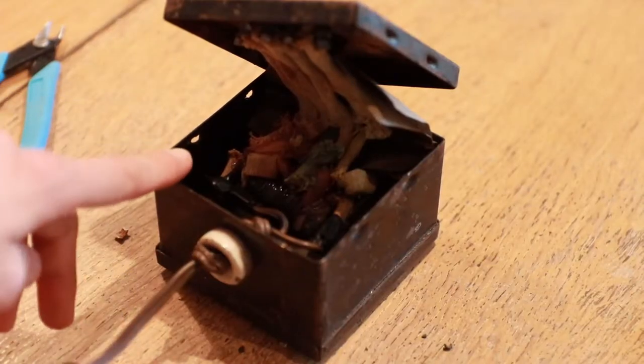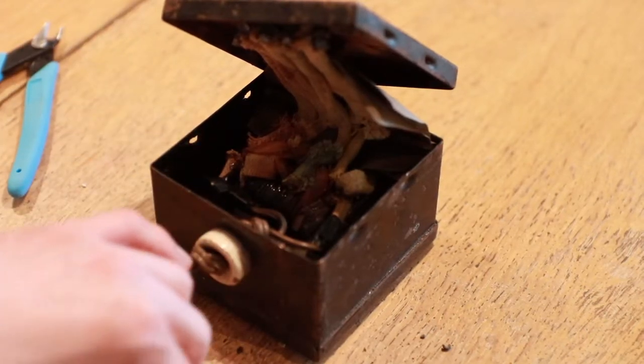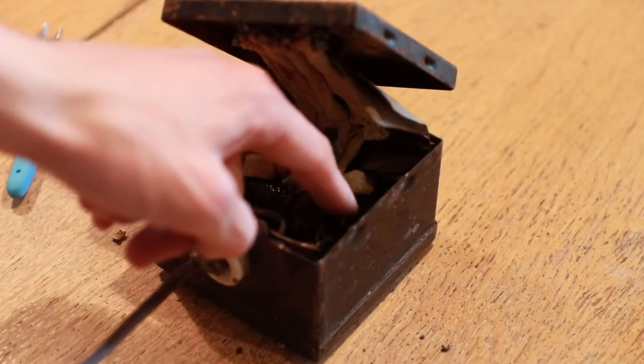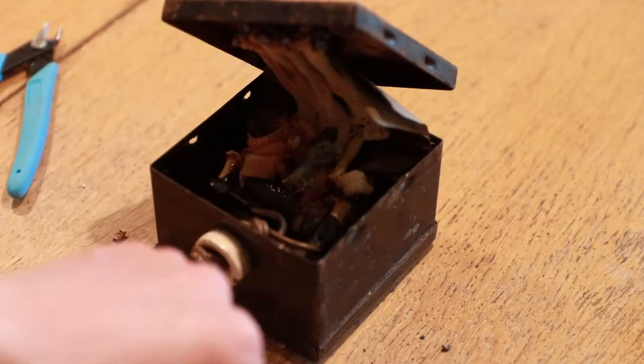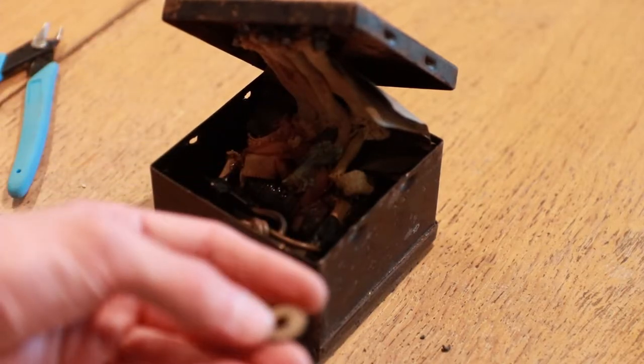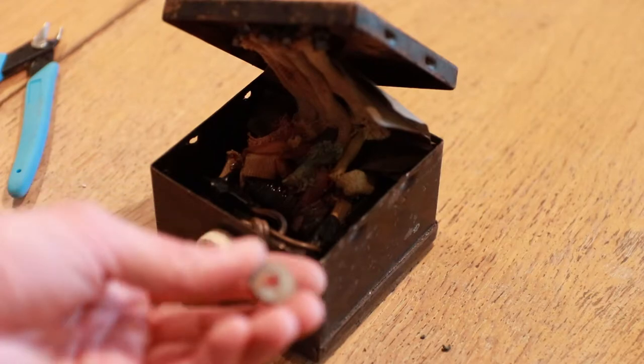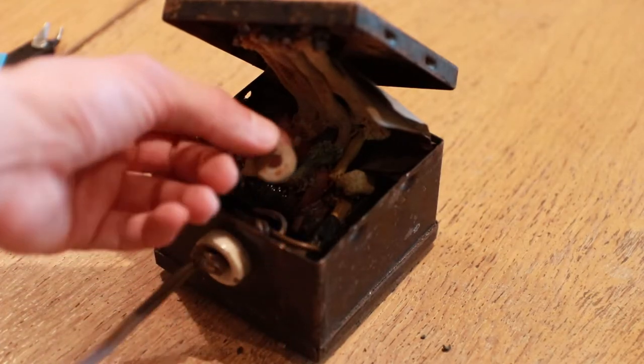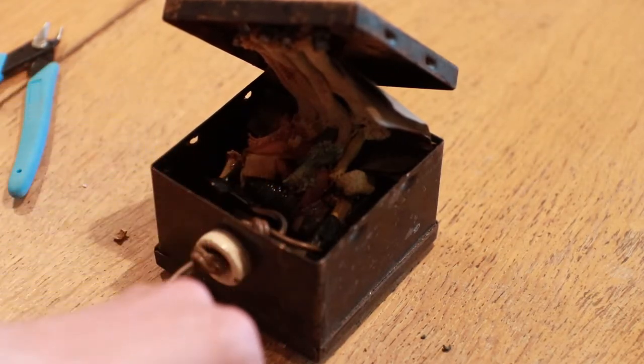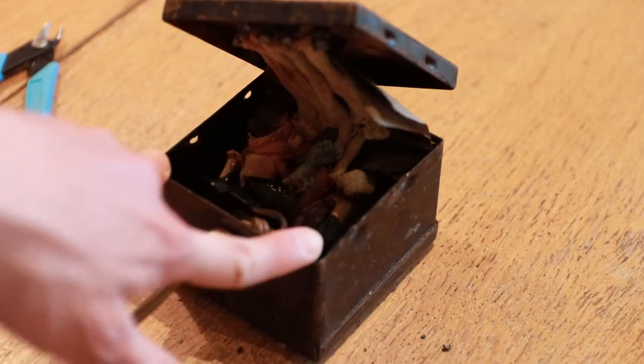So I overturned the container and a few things fell out. These are the receiving nuts that actually go through the transformer and hold the bolts in place, and it looks like the transformer was sitting on these paper insulator washers. So it's going to be important to be sure that the transformer is not sitting flat on this metal when it's in service.